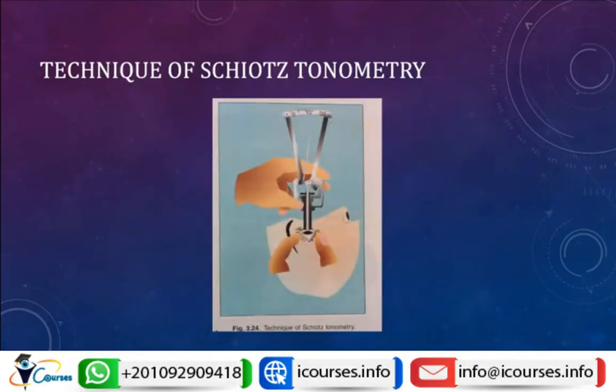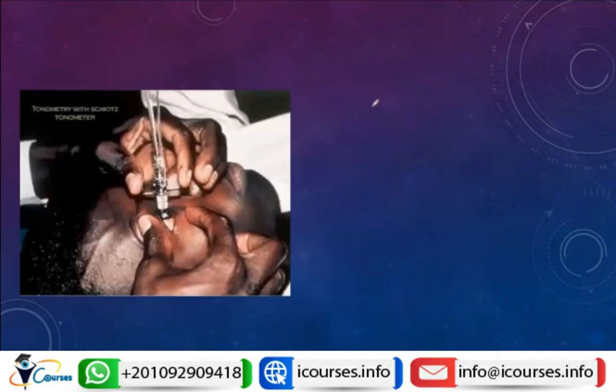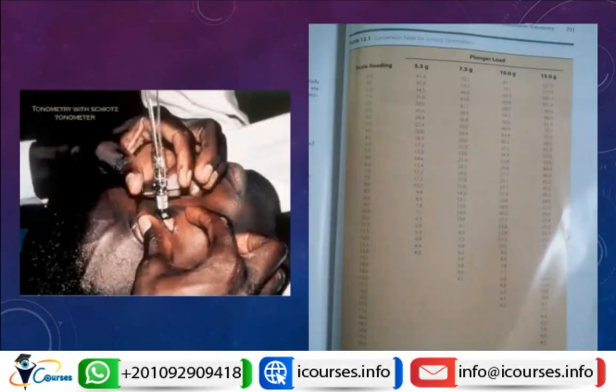Let's assume, for example, we are now putting a weight of a certain amount, and the scale is pointing to 30. Then we compare this 30. This is not the intraocular pressure, but we compare it to an intraocular pressure reading through a table. So we put the weight; if, for example, the weight is 5.5 gram and the scale reading is 10, then the pressure inside the eye is 7.1.